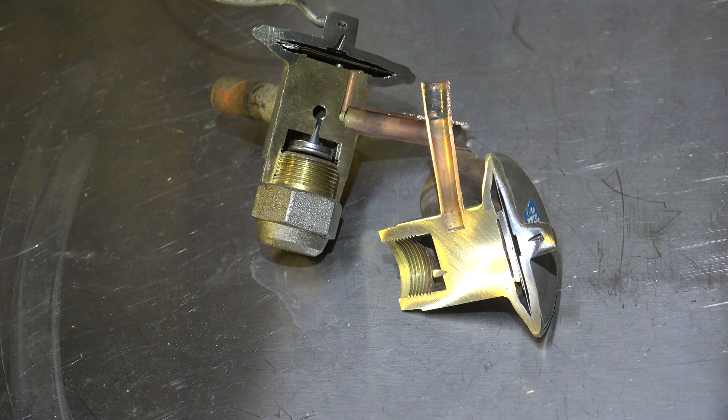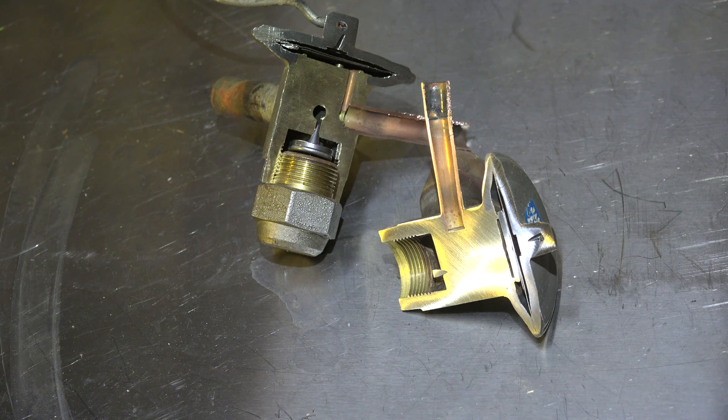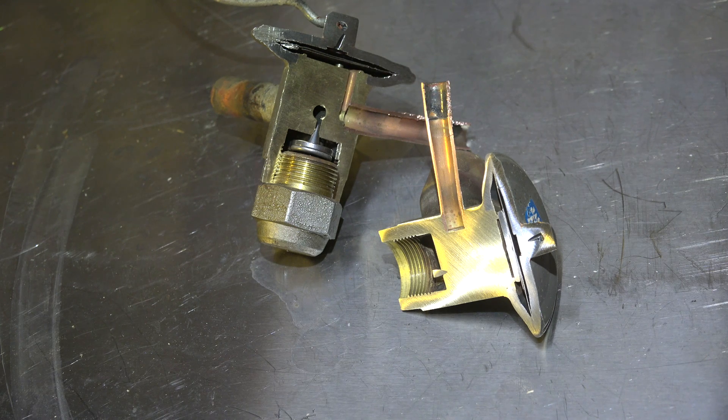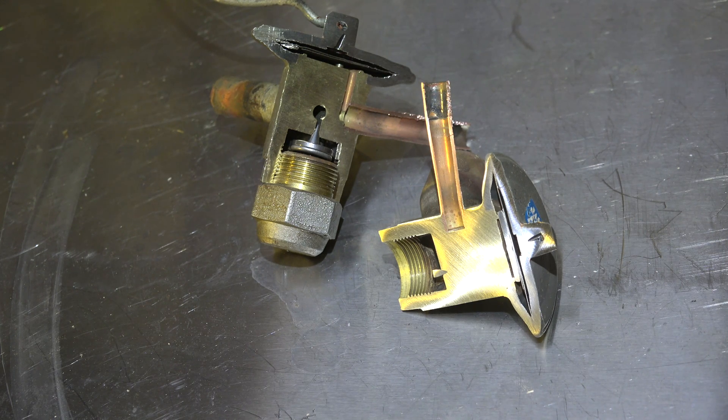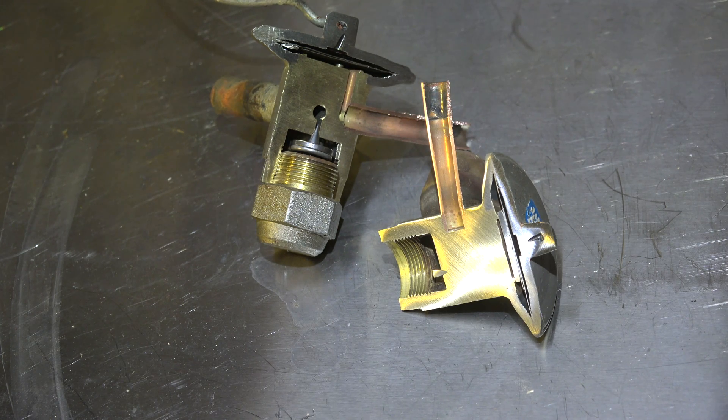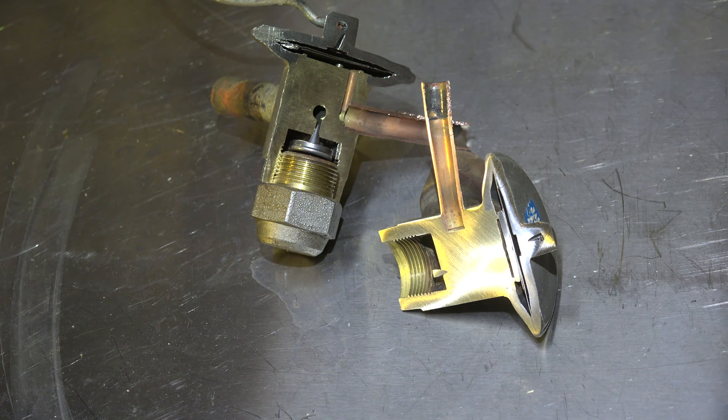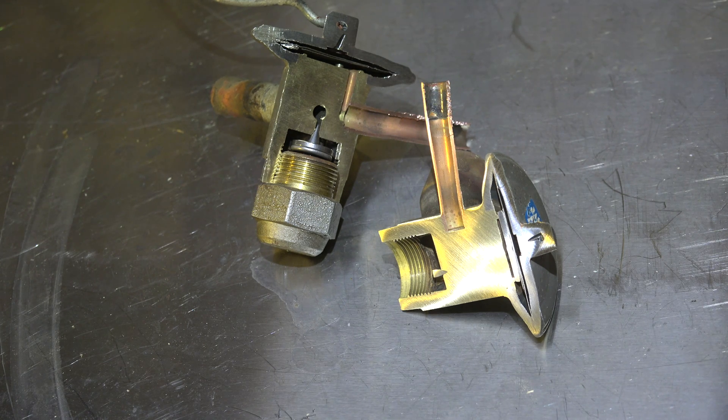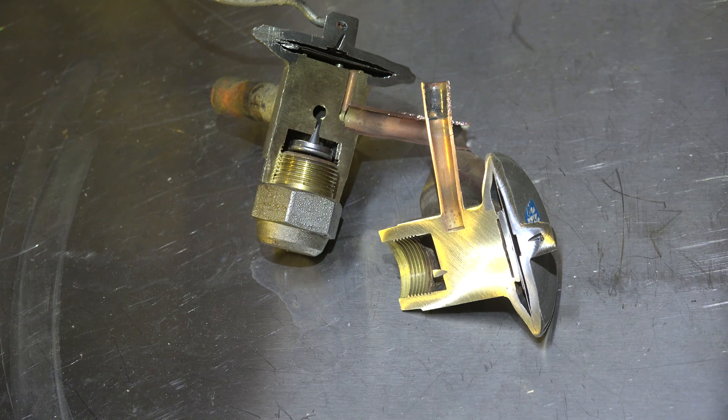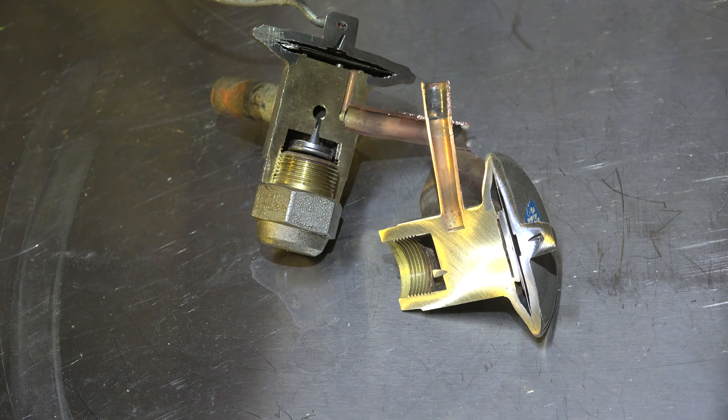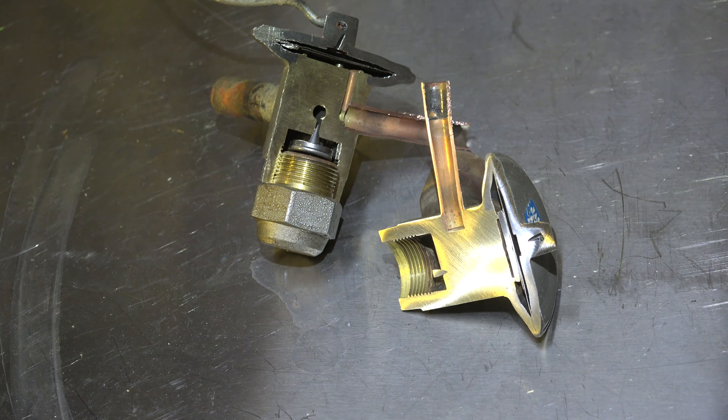So what do we do? We'll put a hard start kit on it. So with a non-bleed TXV, you're going to need a hard start kit.